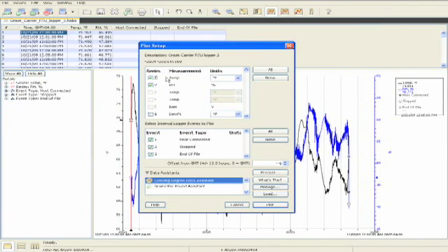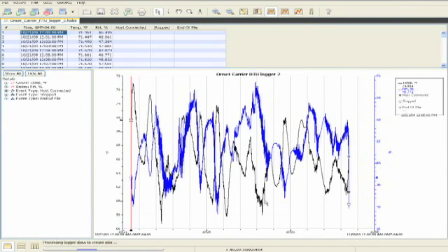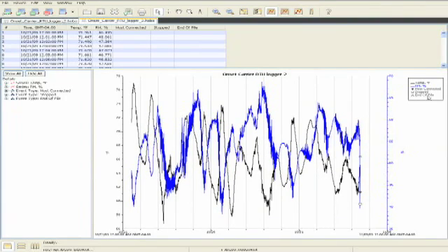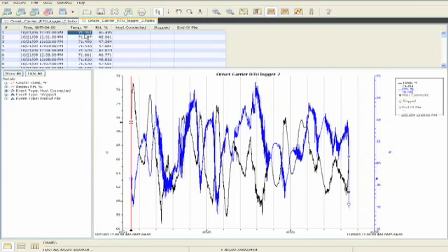Now logger number two, we mounted in the return air temperature of the rooftop unit. It was also reading our relative humidity percentage, and we'll plot those two points. And here's our graph of that. Again, we have the temperature in black, relative humidity percentage in the blue. Our logger was started on the same date, same time as logger number one. Our return air temp, which also we could call our space temperature, was 71 degrees with 46% humidity in the space.